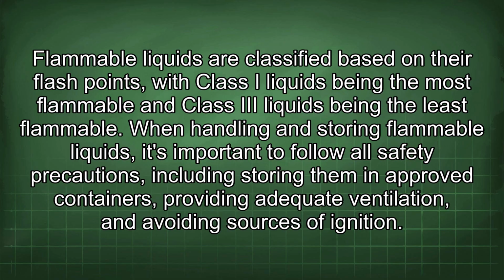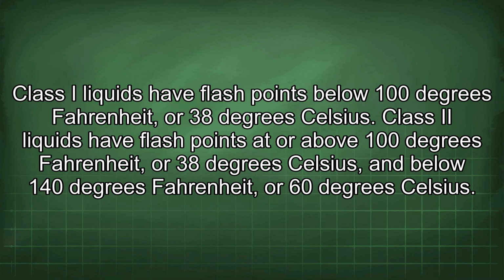When handling and storing flammable liquids, it's important to follow all safety precautions, including storing them in approved containers, providing adequate ventilation, and avoiding sources of ignition. Class I liquids have flash points below 100 degrees Fahrenheit or 38 degrees Celsius. Class Roman II liquids have flash points that are above 100 degrees Fahrenheit or 38 degrees Celsius and below 140 degrees Fahrenheit or 60 degrees Celsius.